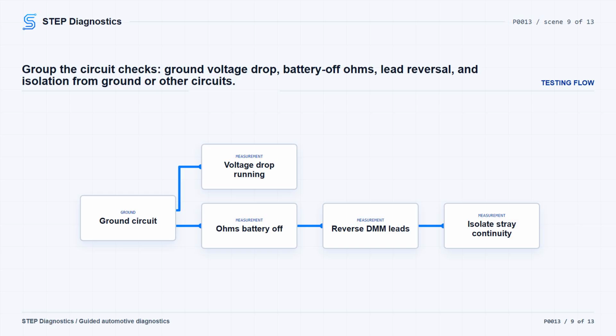To check for unintended continuity to ground, disconnect both ends of the circuit and measure between the suspect circuit and ground. Resistance should be greater than 10,000 ohms. To check for unintended continuity to another unpowered circuit, disconnect both circuits and measure between them. Again, resistance should be greater than 10,000 ohms.